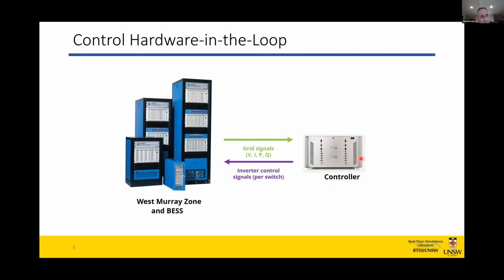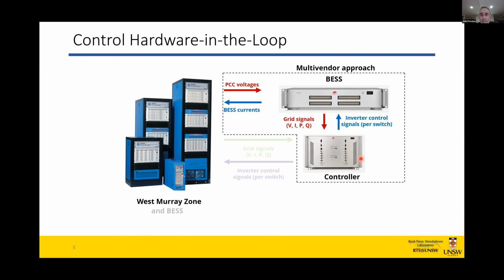We did couple up 3 different types of hardware in the loop systems in order to do this: an RTDS system, an Opal RT system, and a Typhoon HIL, all operating at slightly different sample rates. The power system runs at 50 microseconds. The inverter is represented by a system that operates at about 2 microseconds, and then the inverter controller at a microsecond, which is about as good as you can do with the current technology.